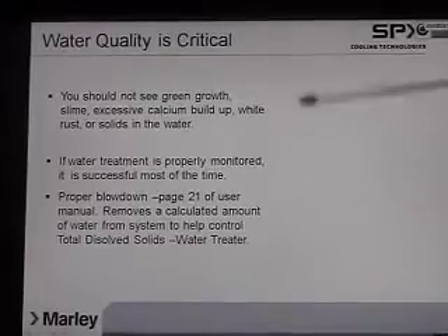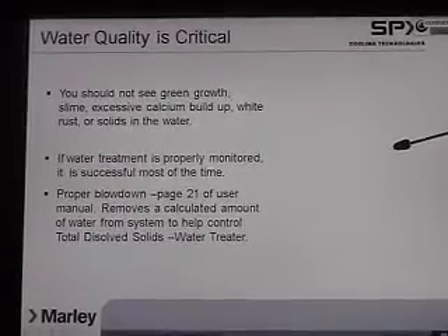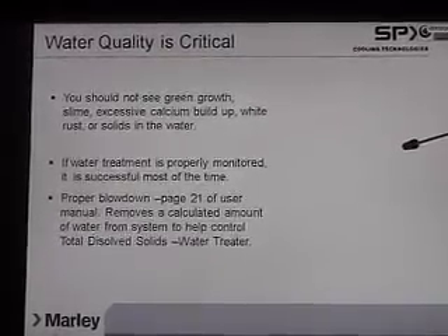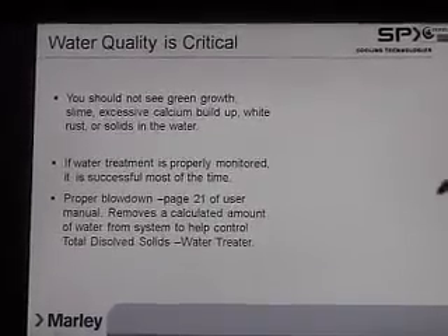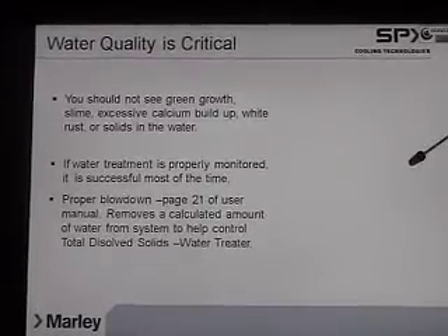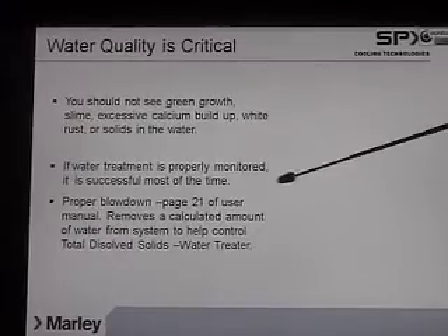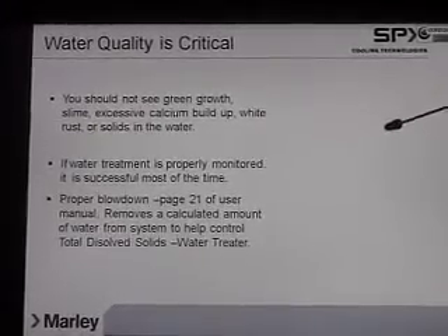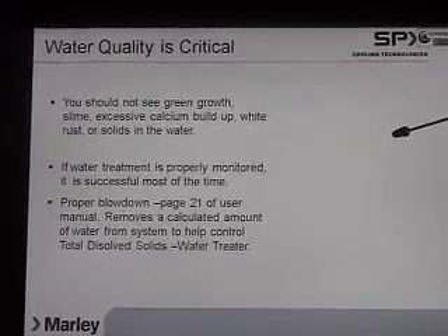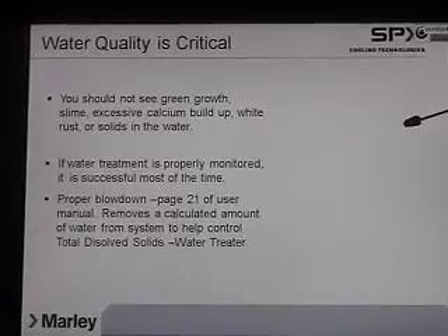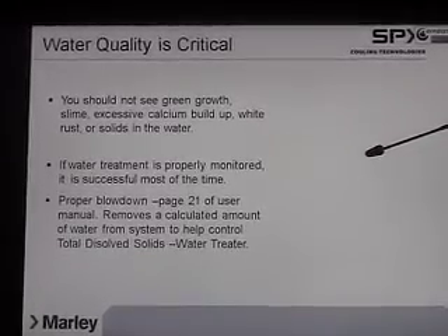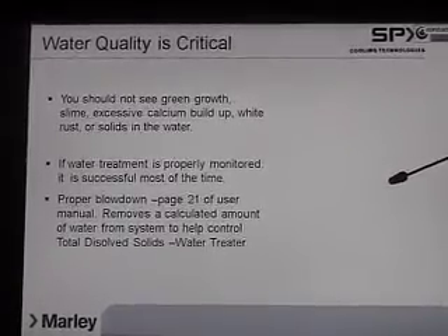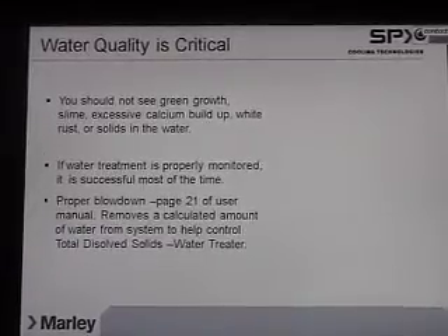One of the other things that the water treater will do, besides clean, biocide, take care of algae, and prevent scale, is manage your blowdown of your cooling tower water. This just removes a little bit of water and helps manage the total dissolved solids in the condenser water.